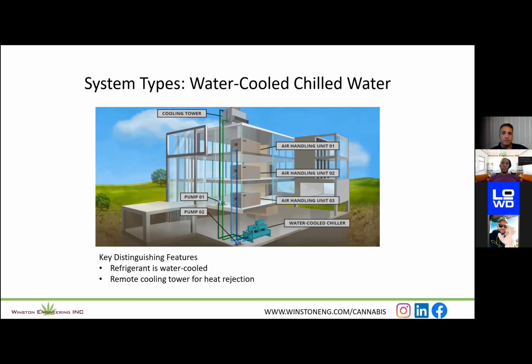Okay. And the way that you can determine water-cooled chill water is that there is a cooling tower on the project, right? So you have your chiller here and in this image here in the basement. And effectively you have two loops of water: one going from that chiller to the building, effectively distributing cold water, bringing it back warm. And then you have another loop of water that's going from the chiller to the cooling tower. And what's happening is you are transferring the heat from the building to the pipes that go out to the cooling tower to reject that heat to the atmosphere. And the refrigerant is water cooled. That's the real distinguishing feature here.